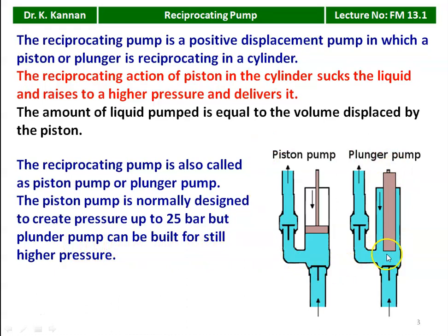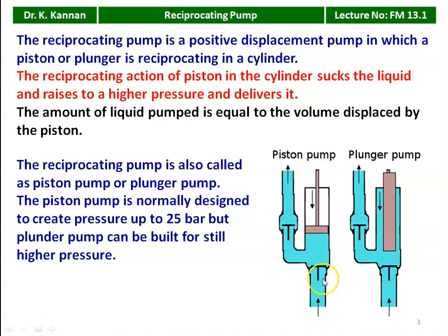Looking at the two diagrams — the first is the piston pump and the second is the plunger pump. There is a piston reciprocating inside the cylinder, with an inlet valve which is a one-way valve. When a vacuum is created in the cylinder, the valve automatically opens and liquid is admitted. When the piston moves downward, the pressure rises, the valve closes. On the other side, when pressure increases, the delivery valve opens and liquid is discharged to the delivery pipeline. This is the suction pipeline and this is the delivery pipeline.